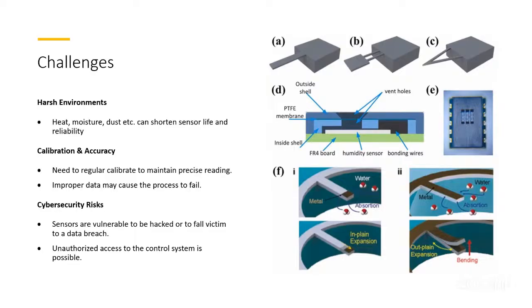And secondly, another challenge: calibration and accuracy. Every one of these sensors, like the pressure sensor I mentioned before, needs to be calibrated. Usually it is a job done by the technician. Usually it is a zero and span calibration, or what I can call maximum and minimum calibration, to help the sensor know its own accuracy perfectly and carry out its measurement perfectly. So this calibration varies per manufacturer.